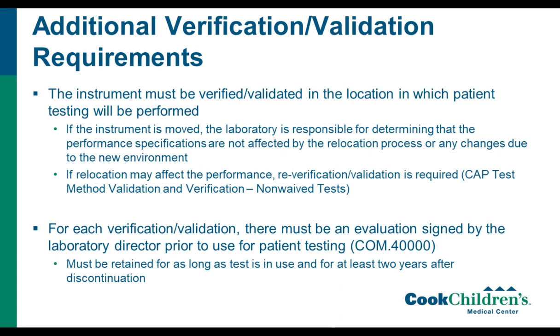For each verification or validation that's performed in the lab, there must be an evaluation that's signed by the laboratory director prior to use. And so this is a summary. We also, in our lab, put all of the data with that as well in a binder, and then that must be retained as long as the test is in use and for at least 2 years after a test is discontinued. So make sure you have all of those documented, and then some CAP inspectors come in and like to look at the validation verification summaries.